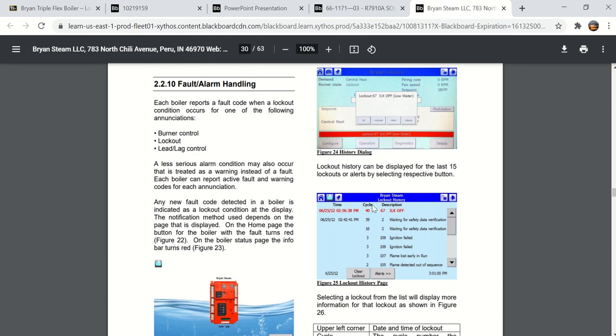Here is the fault history. Tells you at what time, what cycle. For this fault right here, the ignition failed, and the cycle here, you see cycle 3, cycle 3, cycle 3. That means that flame was lost in early run. Somebody pushed the reset button. It tried to ignite. It didn't ignite. Somebody pushed the reset button again.